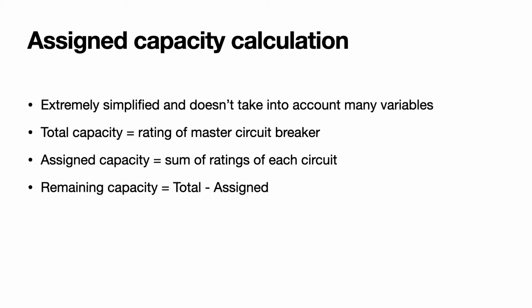Now the assigned capacity is the sum of the ratings of each circuit, or rather the rating of the circuit breaker for each circuit. Again, we're assuming that the electrician who did the installation of the electrical service at the house correctly sized the circuit breaker for the ratings of the wiring and the electrical outlets in each circuit. So then the remaining capacity is simply the total capacity minus the assigned capacity.